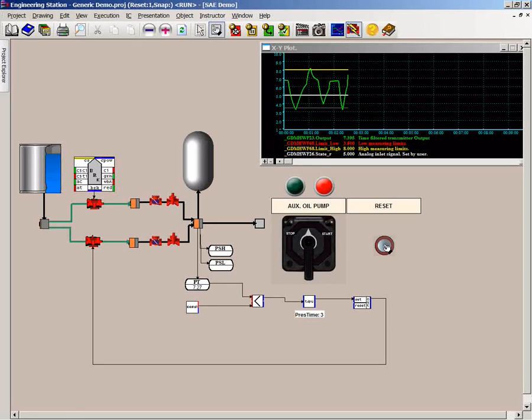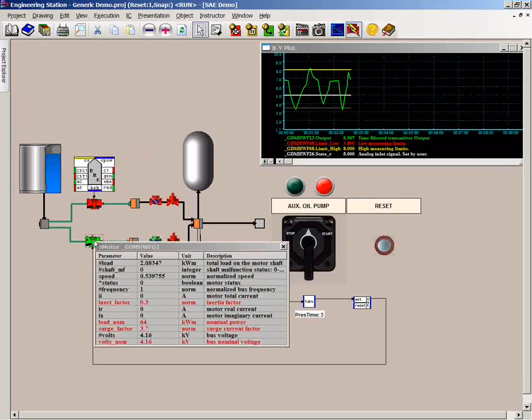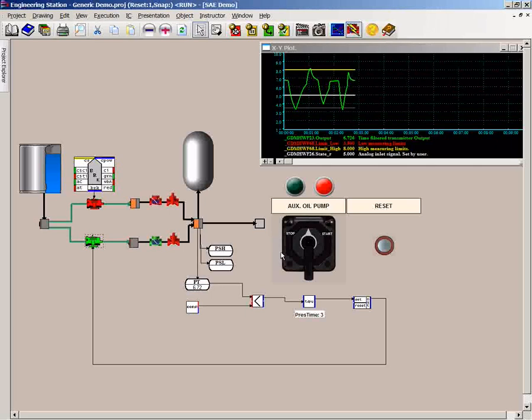we'll replace the current pump, the standby unit, with a much faster acting unit, shown here in a simplified way by putting a smaller inertia factor. Running the same scenario again now results in a system which survives and does not trip, but perhaps comes too close to our safety margin. We can now, for example, reevaluate our control system.